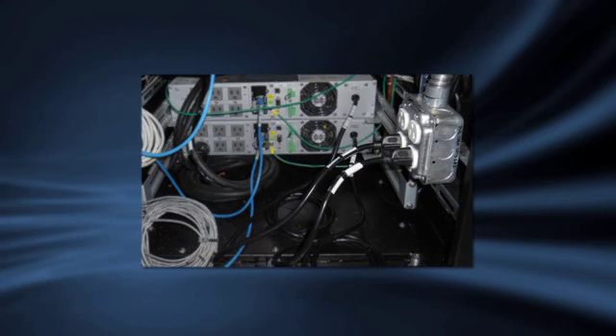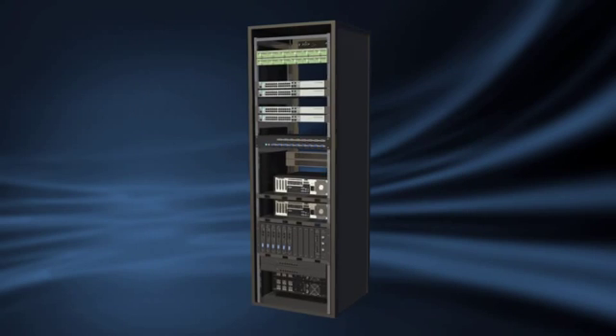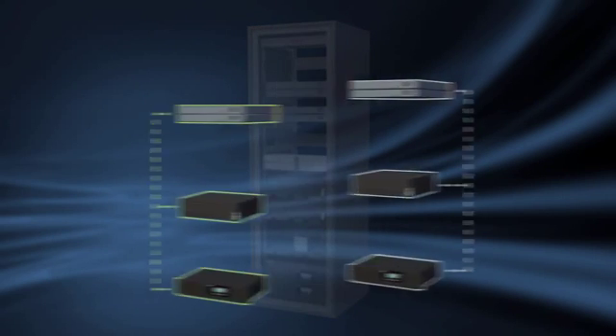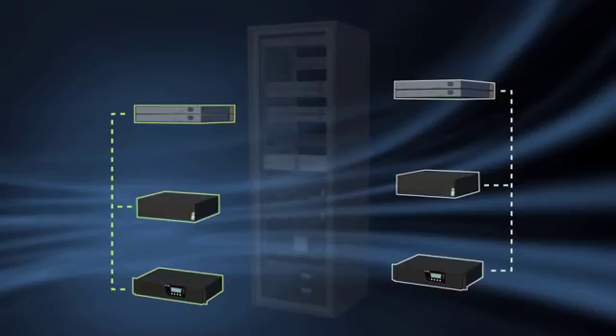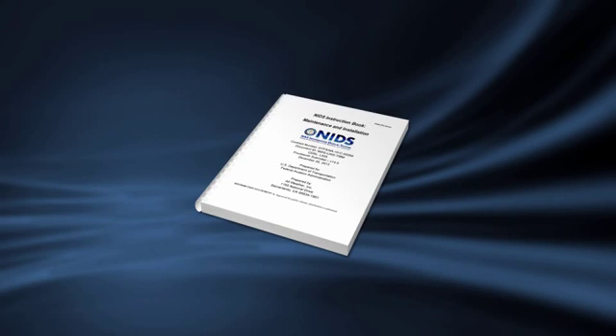Power is provided via 2 external power sources and through 2 UPSs. The equipment is evenly divided between each of these power sources and UPSs and is regulated by the automatic transfer switch. Should power be lost on one side, the ATS will draw power from the other source until it can be restored. To make sure you minimize downtime, verify the failover protections are working by following recommended procedures in the TIB and other technical documentation.